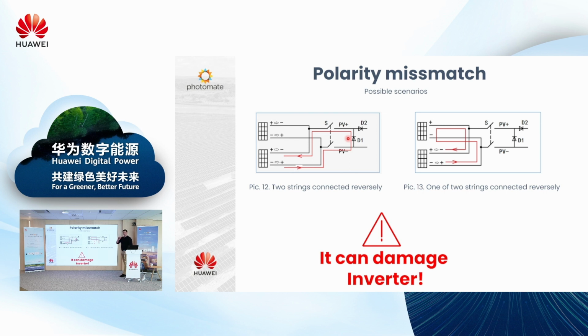The dangerous situation is when you have the opposite situation, when only one PV string is connected reversely, because this current will flow even if you don't turn on the DC switch on the inverter. Reasonable thinking should tell you that if you haven't closed the circuit with the DC switch, there's no chance current is flowing, but it actually is. So the DC switch is off and you have the full short circuit current going through those PV modules inside the input of the inverter.